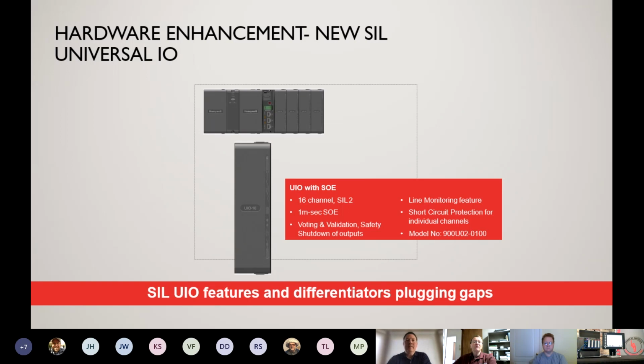But this is a newer I/O module that Honeywell came out with, and like I said, it really helps. If you have a typical system that might need 8 slots on the HC900 to do the control, in the past you had to have separate analog ins and analog outs. Well, now you could probably shrink wrap that into a 4-slot chassis and do that with a universal I/O module instead.